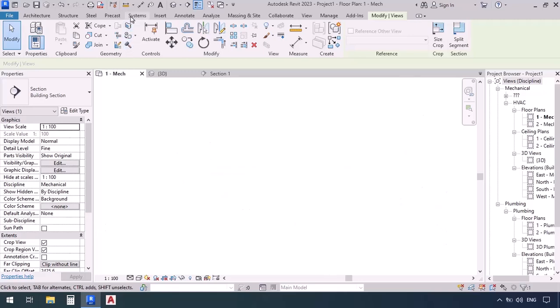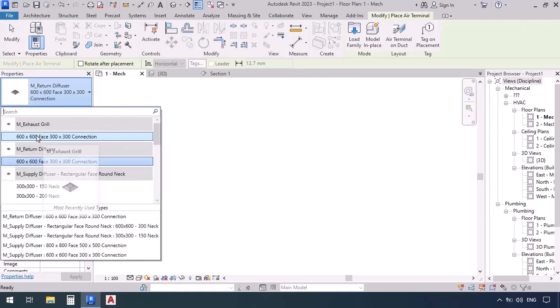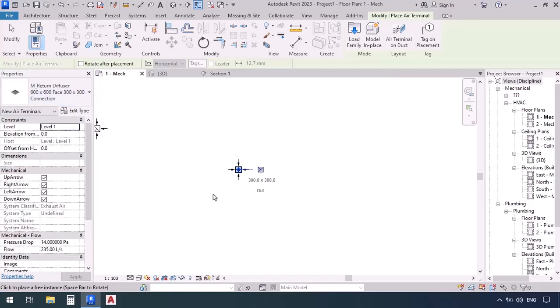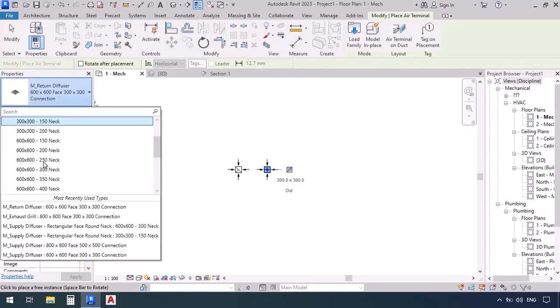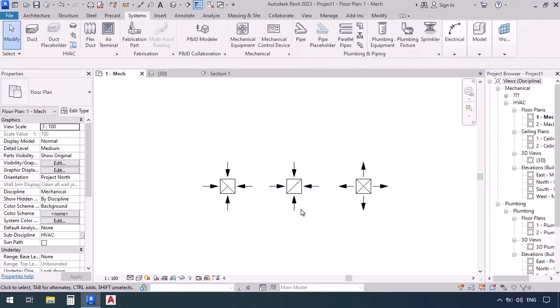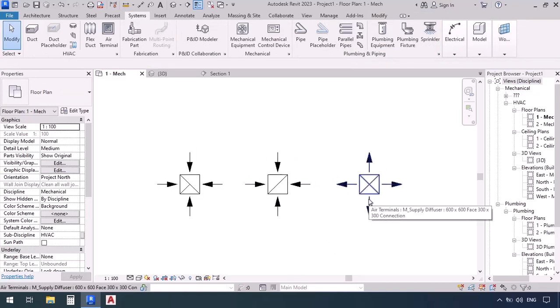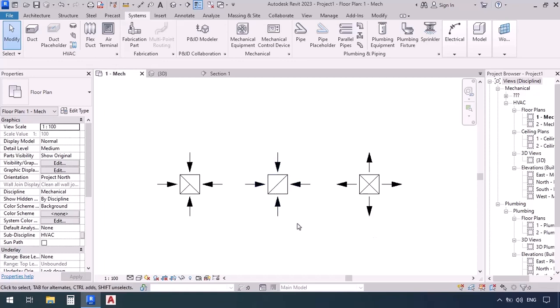Let me tell you some other things. Go to the systems tab and air terminal — place an exhaust terminal, then a return, then a supply. The supply terminal has two crossing lines in the middle indicating the diameter and arrows pointing outward — those are supply indicators. The return terminal has one diameter line with arrows pointing inward. The exhaust terminal has one complete diameter line, another in half, and arrows pointing inward. Through knowing their appearances you can recognize which type each terminal is.